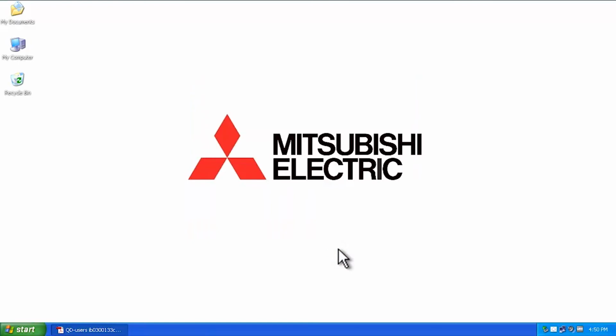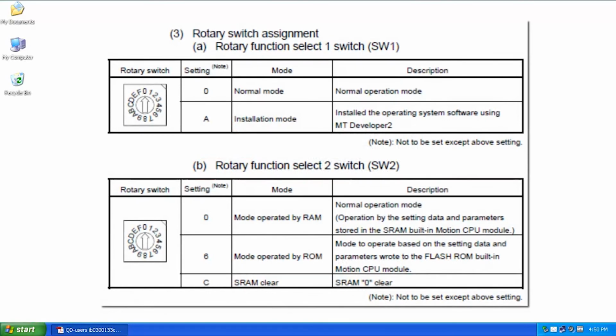Now, in order to begin programming, you're going to have to turn the power off and then look at the rotary switches on the front face of the motion controller. You'll see two rotary dials, SW1, SW2. In order to exit the installation mode, with the power off, move the rotary switch 1 to position 0. Now, for switch number 2, you'd select that and put it into position 0.